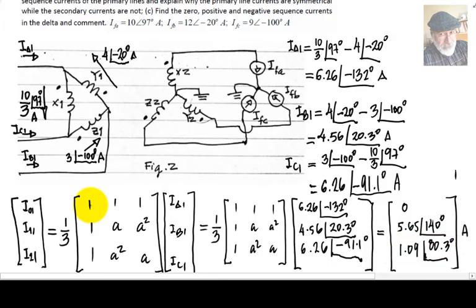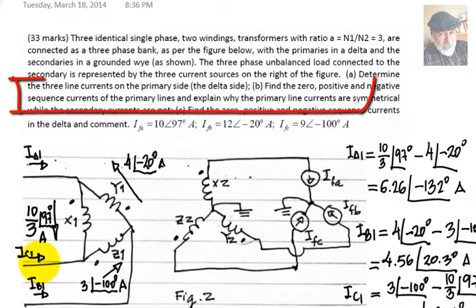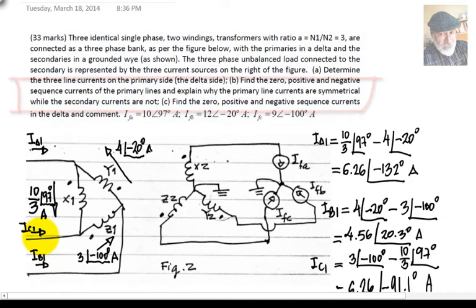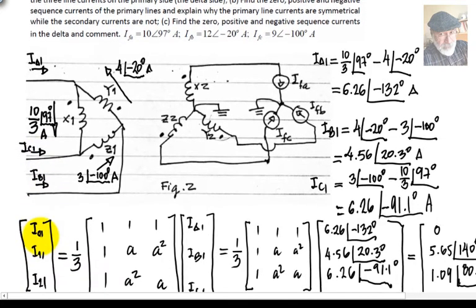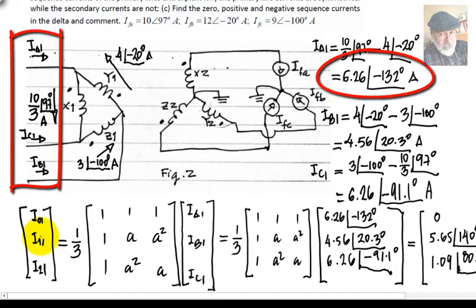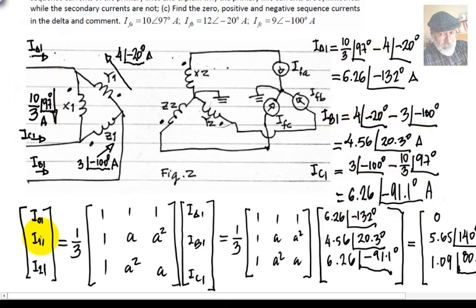Part B also asks something else that is a bit misleading on purpose: explain why the primary line currents are symmetrical while the secondary currents are not. The answer is: the primary line currents — 626, 456, and 626 — are not symmetrical. So the answer is simply no: the primary line currents are not symmetrical. Now let's go to Part C.